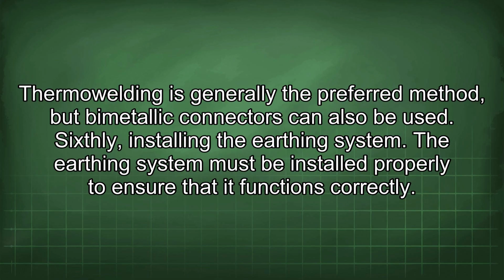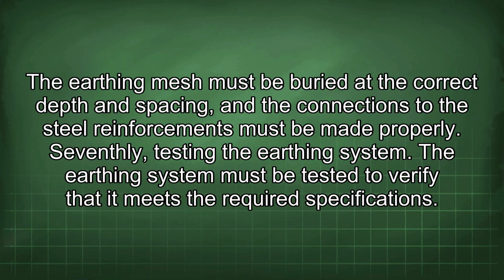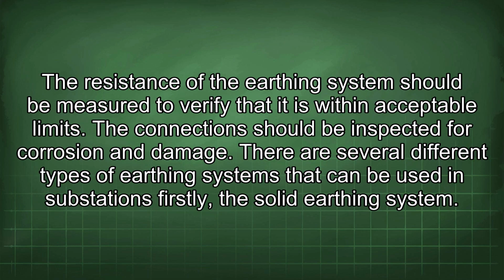Sixthly, installing the earthing system. The earthing system must be installed properly to ensure that it functions correctly. The earthing mesh must be buried at the correct depth and spacing, and the connections to the steel reinforcements must be made properly. Seventhly, testing the earthing system. The earthing system must be tested to verify that it meets the required specifications. The resistance of the earthing system should be measured to verify that it is within acceptable limits. The connection should be inspected for corrosion and damage.